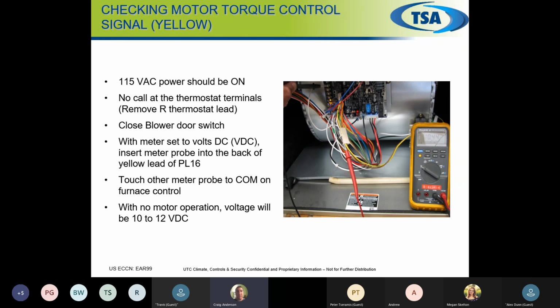So now that we know coming out of the board and going to the motor, we have that DC voltage. We have our 115 volts on our power in. So we know the board is good. The board is doing the job. So now we want to see what the motor is doing. So similar testing that we've done on the brown, we want to do on our yellow.